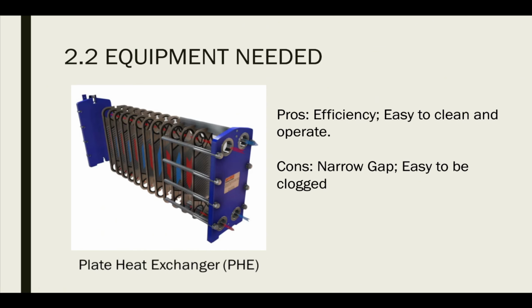I will now present section 2.2, the core equipment required for our heat recovery system. We evaluated 4 key categories of equipment. Let me briefly outline their pros and cons. First, for plate heat exchanger, the pros are unbeatable thermal efficiency in a compact footprint and easy to open and clean for maintenance. And for cons, the narrow flow channels are highly susceptible to clogging with fiber solids. This is a critical weakness for our application.